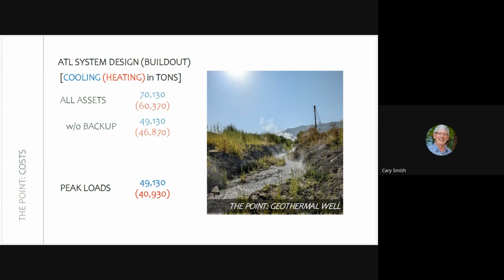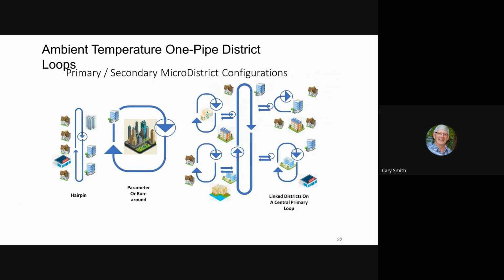So this is an indication that we could really make this whole project a renewable project with a backup for heating and cooling on the peak summer days or peak winter days. Next slide. So we came up with, let's look at a different way to do this. How about a convective loop and a conductive loop that we use? It's a single pipe loop. It's a closed loop system, and there are different configurations. And if you go all the way to the right, you can see that you can link these loops together so that literally one drop of water goes around the entire system. It is able to do it.